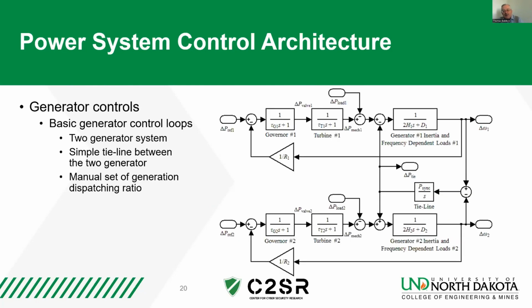Of course, what becomes more challenging is when we start to put together multiple generators. And one of the key points there is how they share load between the generators. And equally well, using set points of voltage so that reactive power can be shared between generators as well. And so what we now do is add to the system the effect of how much power is being produced by different parts of the system, as well as how the frequency is changing in the system. And so we take frequency measurements and feed that back to our system.